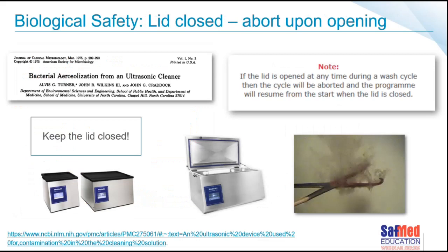When you're using an ultrasonic cleaner, it's quite possible that there will be bacterial aerosolization, and that's a risk. That's why some of the bigger models have a function where, if you open the lid, the sonics will stop working straight away and possibly even abort the cycle, depending on the make and model of the machine. The smaller ultrasonic baths don't tend to have that safety feature, but if you're using those baths for eye instruments or smaller devices, please keep the lid on, else you're potentially exposing yourself to microorganisms.